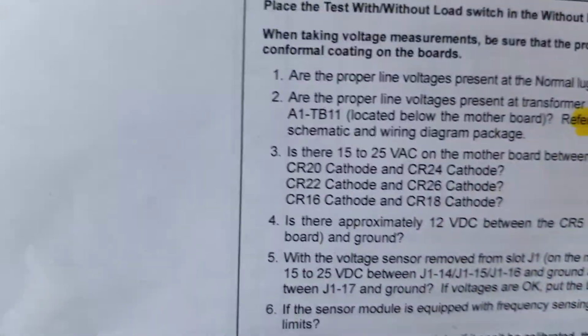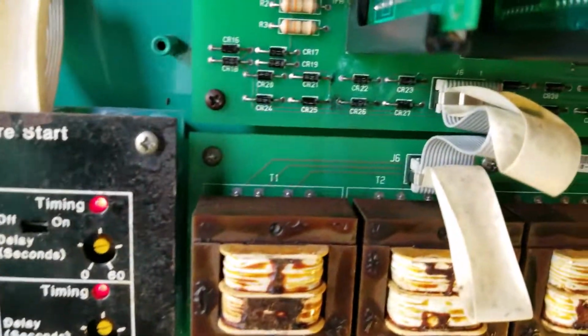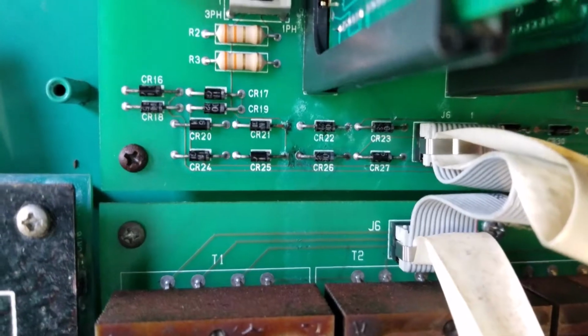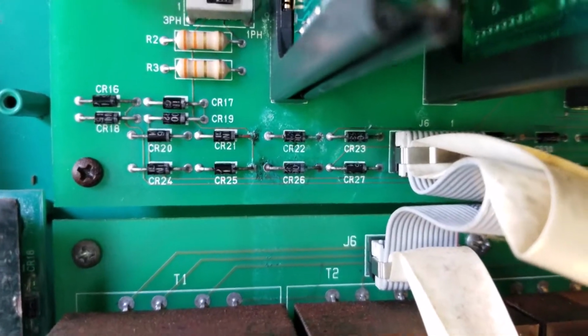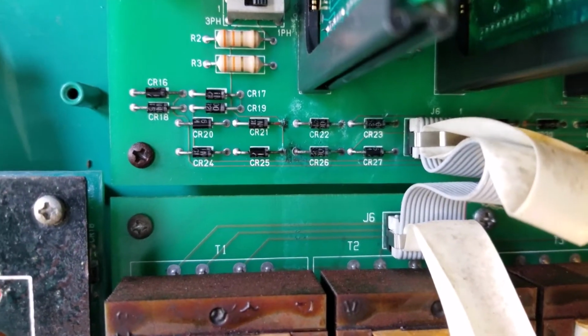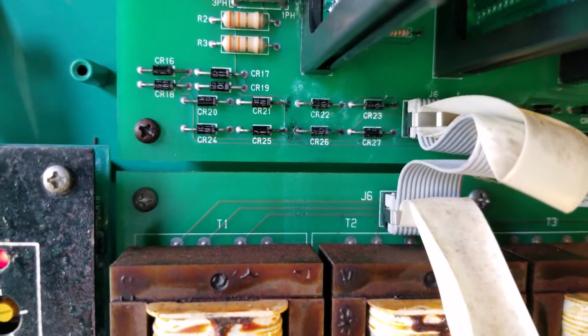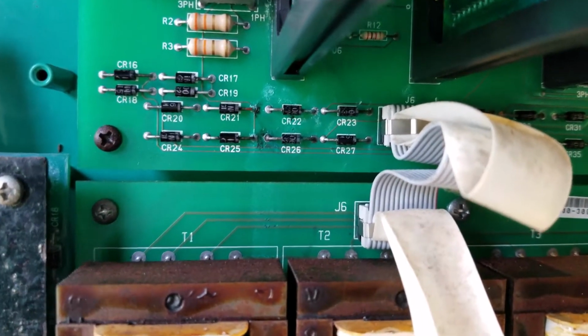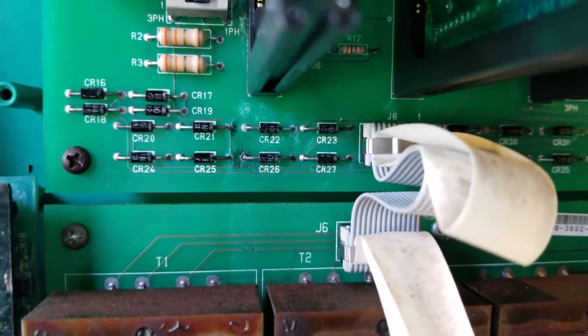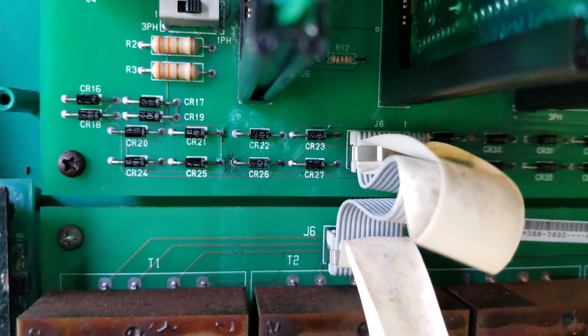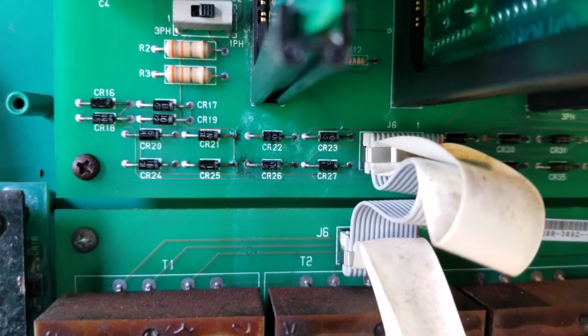Then it gets into some other test procedures for the diodes, right over here, and that test failed. Let me zoom in real close. You can see CR21, 25, 26, and possibly 22 have a lot of corrosion or burn or something. I'm not getting anything up there, so that's a problem.